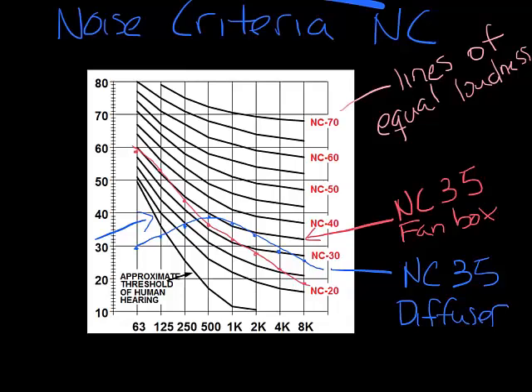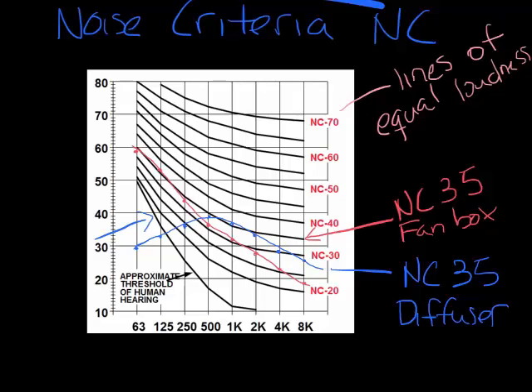Now these two NC curves look very different, but they're both about the same NC, about an NC 35. But you can imagine that these two would sound very different. One would be a low pitch sound, one would be a higher pitch sound. So what an NC graph tells you is how loud the sound is, not necessarily what it'll sound like.